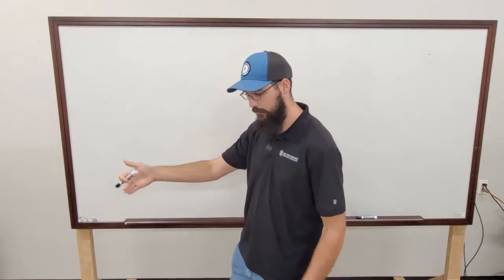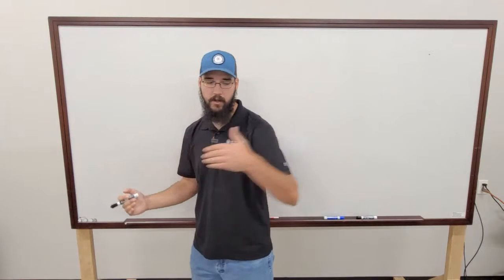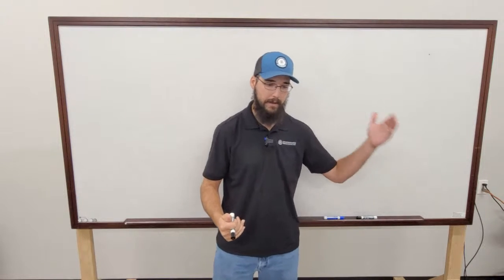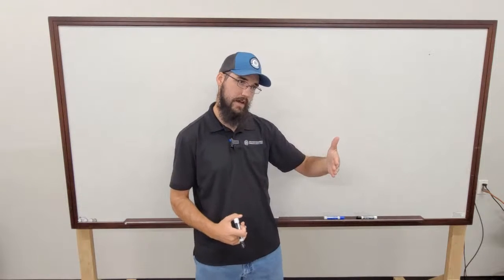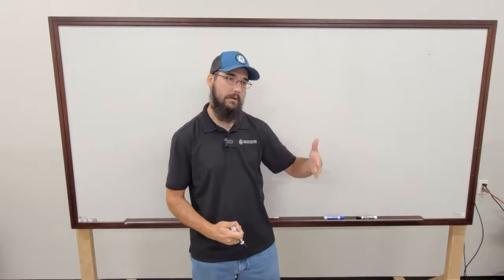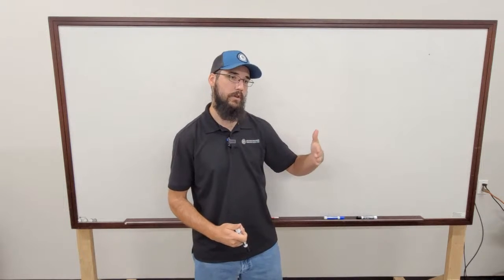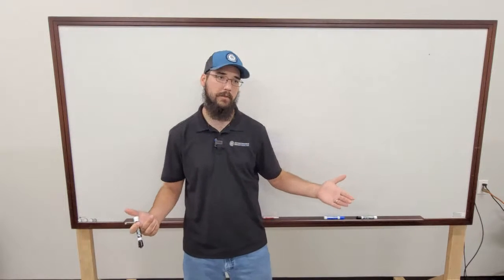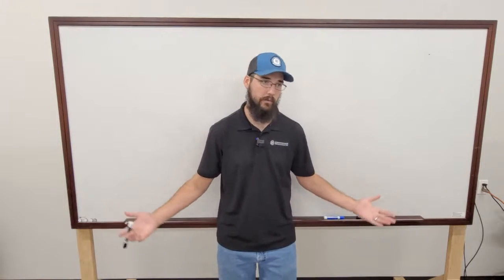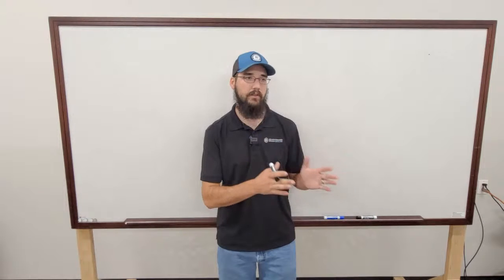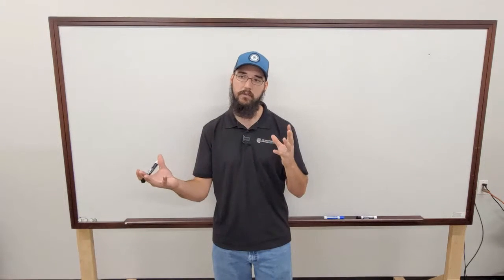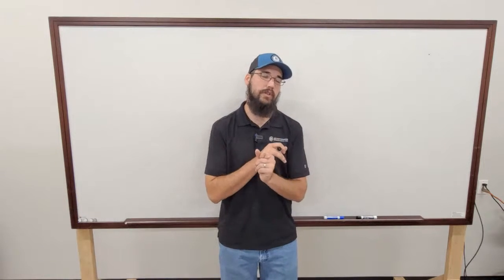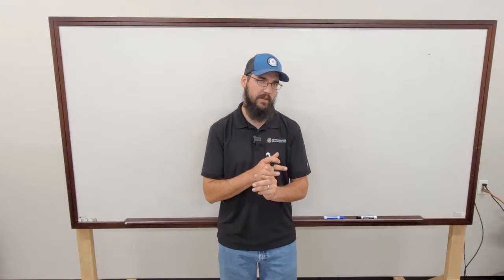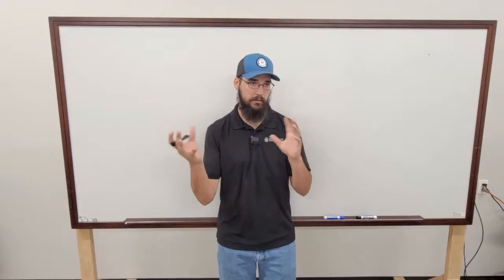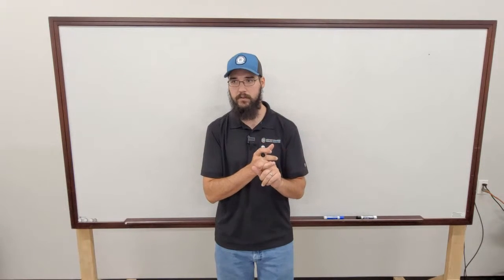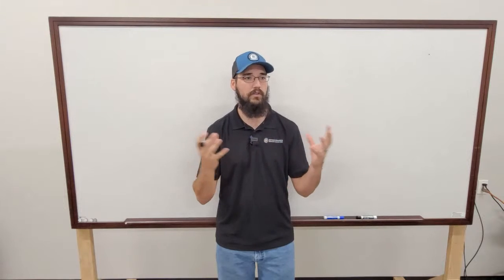So we've got our start stop, we've got our flow, we have our load, we're ready to turn on, and our safeties are good. So we get past the safeties, we've satisfied our minimum flow requirements. Now we've got to decide which circuit turns on. Because most of the time we're dealing with multiple circuits, at least 2, if not up to 3 or 4. Most systems are set to do circuit load balancing based off of, usually I like to do mine off of starts. Some machines I think will base it off of run hours, or run hours will factor into the equation. But my personal preference is basing it on starts. I like to do a balanced start.